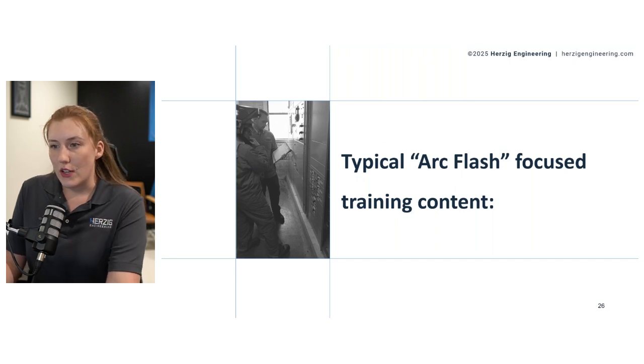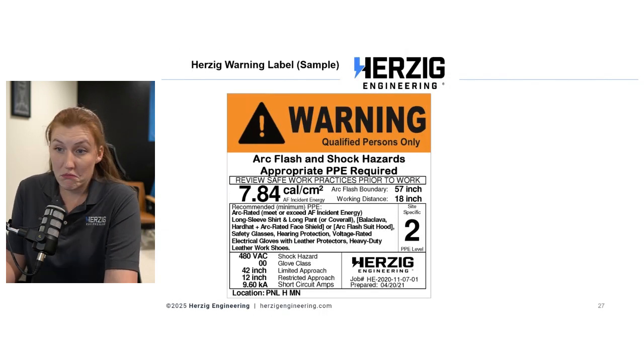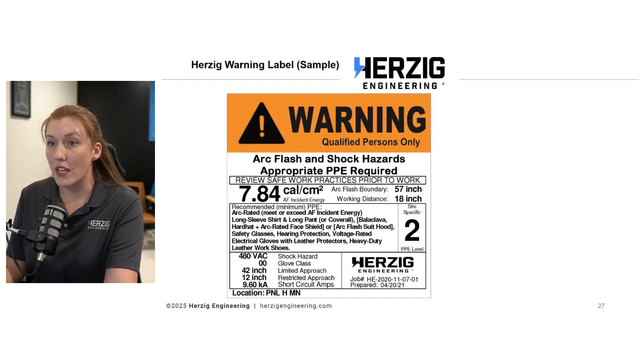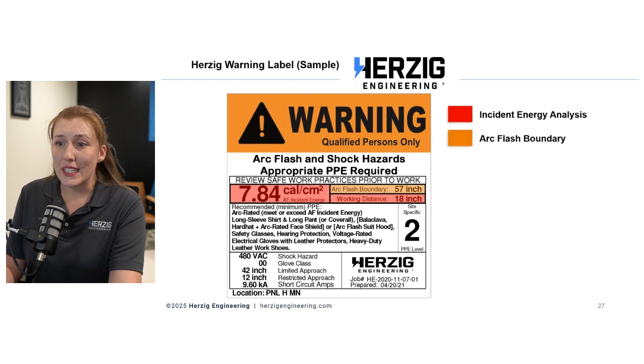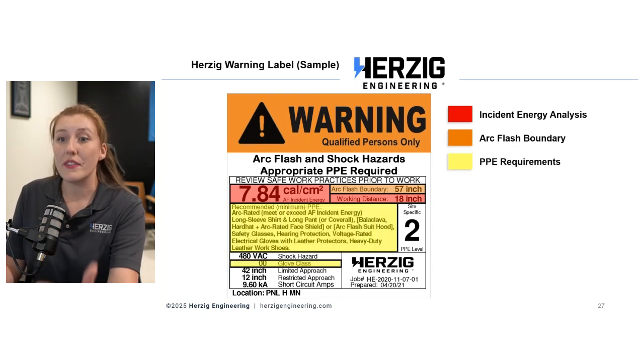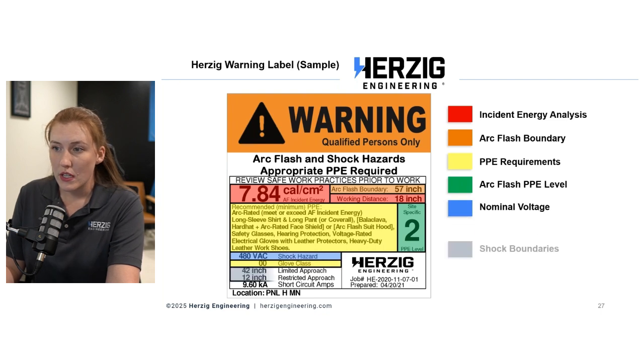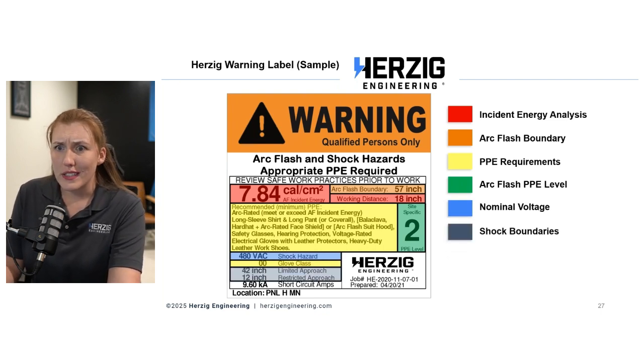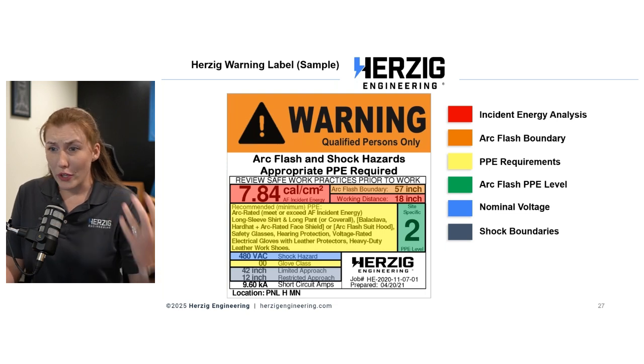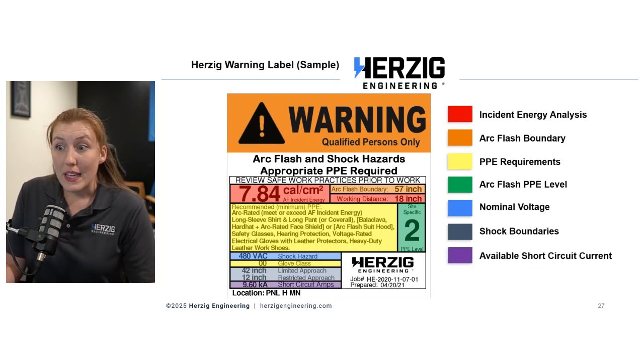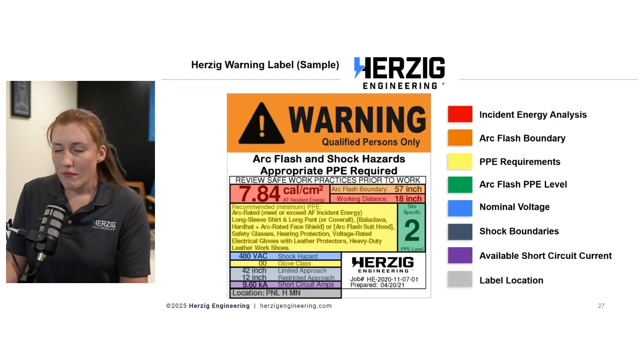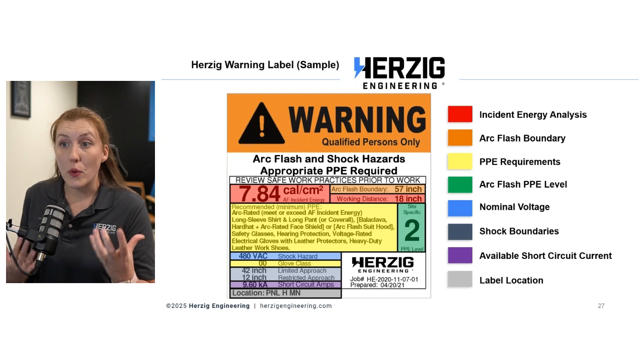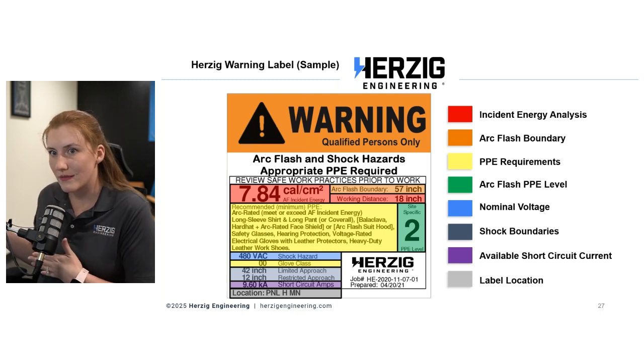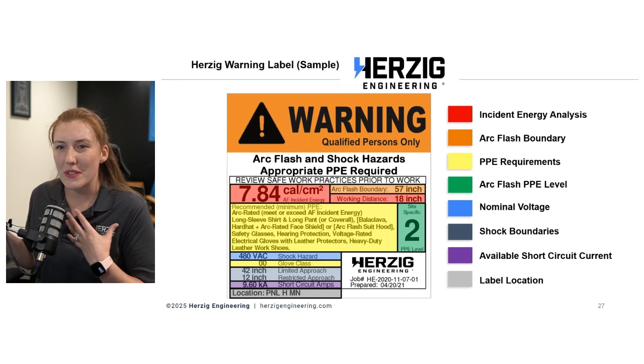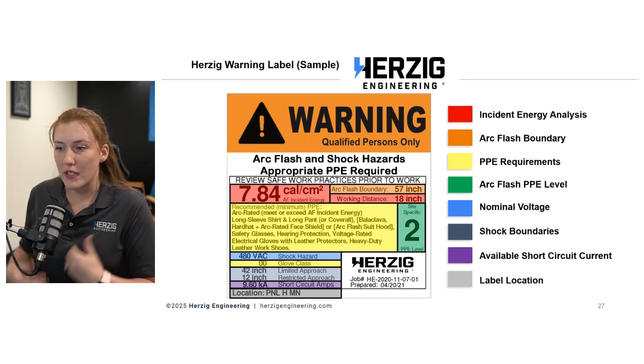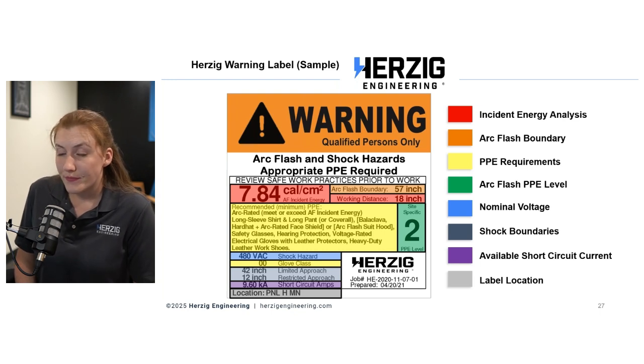So what is typical arc flash training focused on? A lot of times it comes with arc flash studies. If you have a study done, you have to be able to read and interpret the blocks of information on the warning or danger labels. What is the incident energy analysis? What does working distance mean? What is the arc flash boundary? What are the shock boundaries, and how do those apply? What PPE is required for different levels of hazard? All that information should be adequately covered in arc flash training and 70E training. If workers have to use those labels to identify hazards and protect themselves, you've got to train them on it.